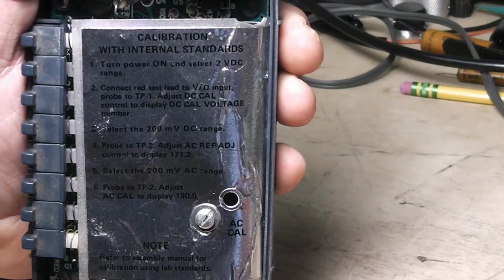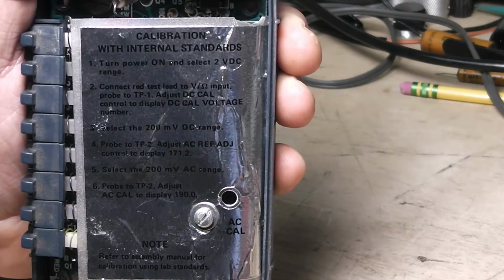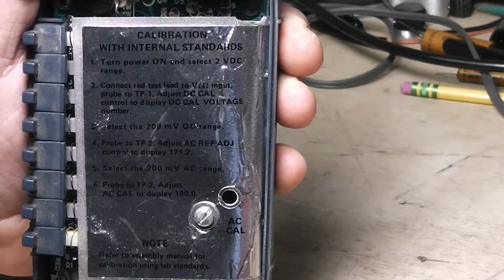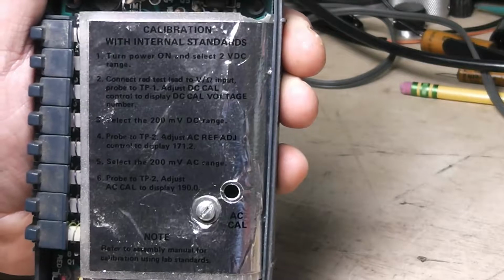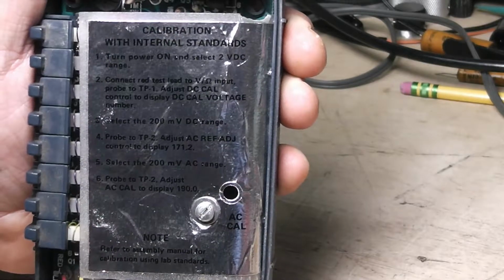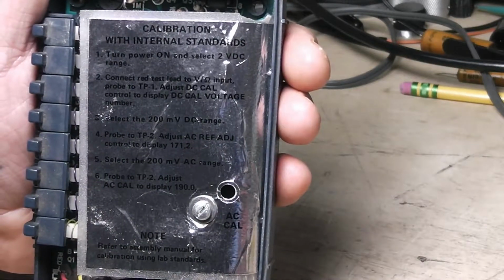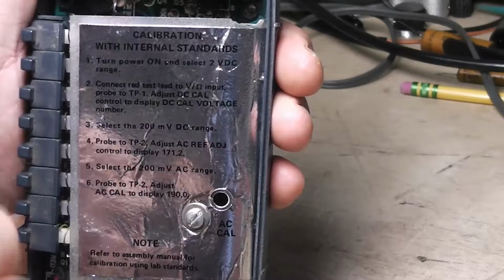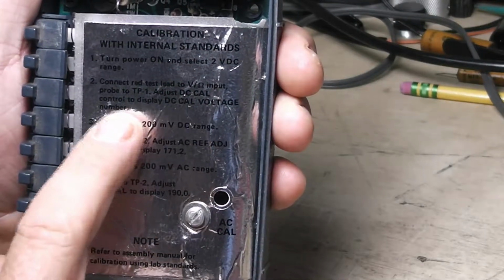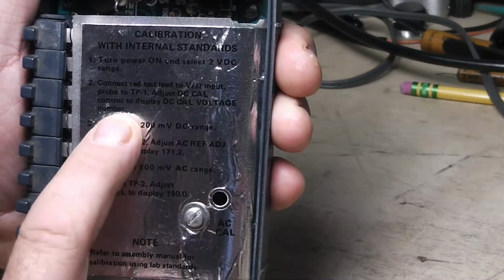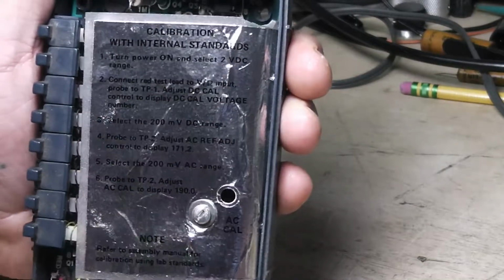That says, calibration with internal standards. Turn power on and select 2 volts DC range. Connect red test lead to volt ohm input. Probe to test point 1, which is the one up here.